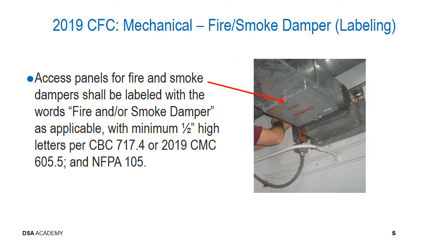Access panels for fire and smoke dampers shall be labeled with the words fire and/or smoke damper on the access panel. The letters shall be a minimum 1/2 inch high, as noted in CBC Section 717.4 or Mechanical Code Section 605.5. All fire dampers, smoke dampers, and combination fire smoke dampers must be installed per the manufacturer's instructions and listing.